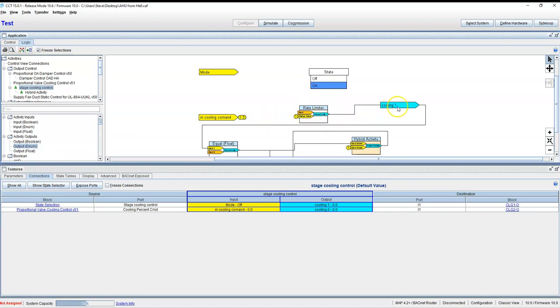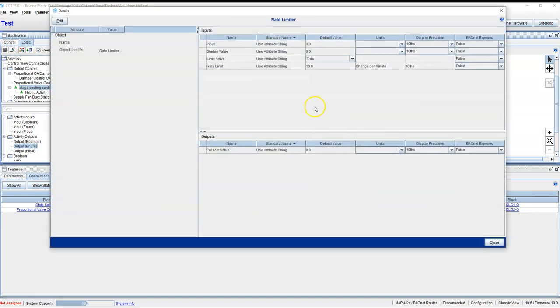That's going to knock down the cooling control from whatever the command is, and it's going to start going down to zero. We did 10 changes a minute—we can jack with that. The lower the number here, the slower it goes.